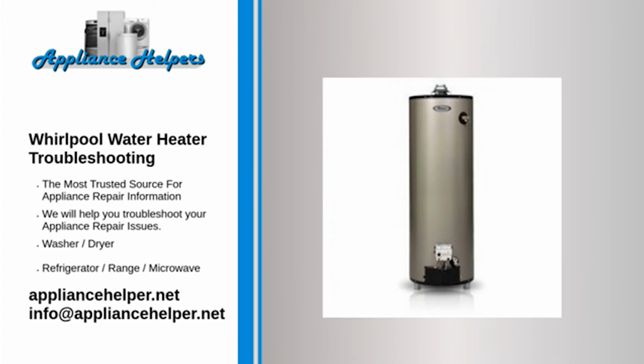Step 6. Troubleshoot water heaters giving warm water or small amounts of hot water. Check the temperature setting. Adjust the setting with a slotted screwdriver if necessary. Set the temperature between 110 and 125 degrees F.